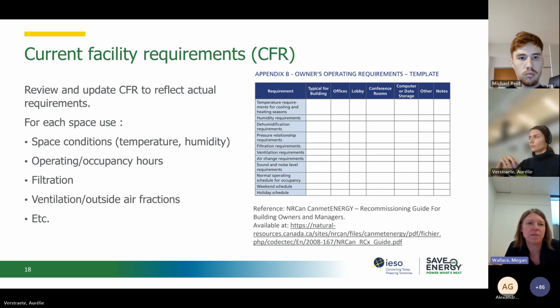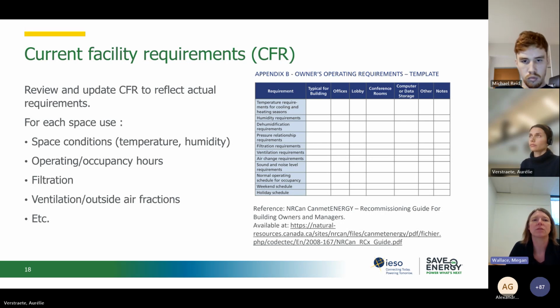Another thing that needs to be done as part of the planning process is to identify the current facility requirements, or CFR. This table is an example of what can be filled out by the owner to identify their requirements for each space type. You'd want to identify the space conditions for each space use - temperature and humidity requirements, operating hours and occupancy, any special air filtration requirements, and the amount of ventilation or outside air.